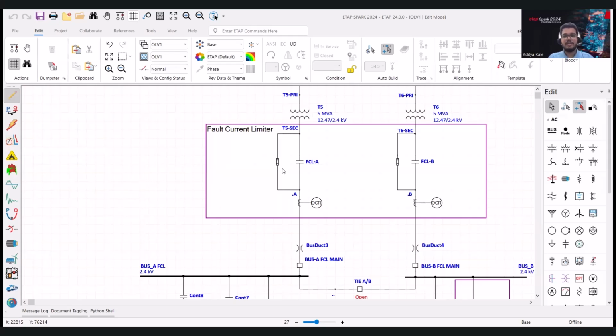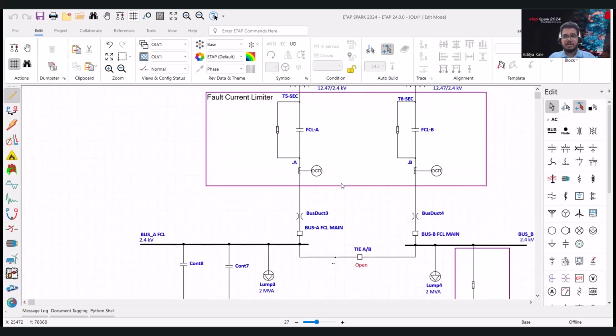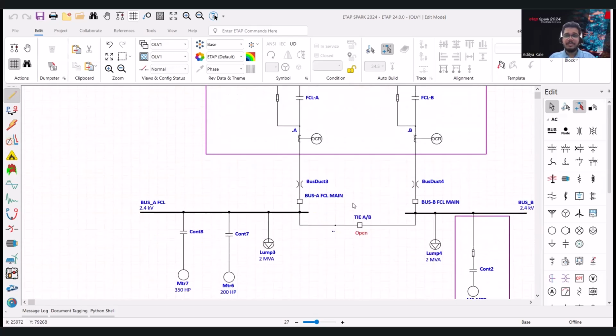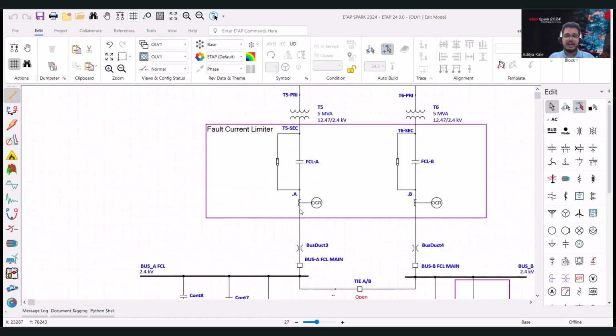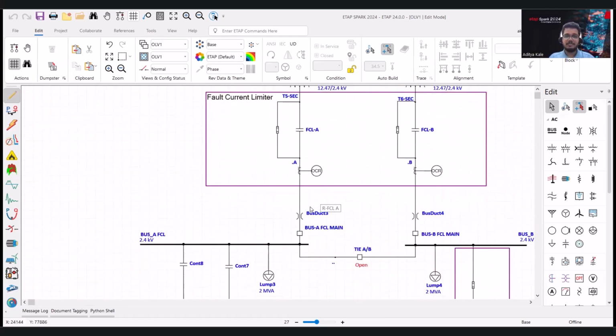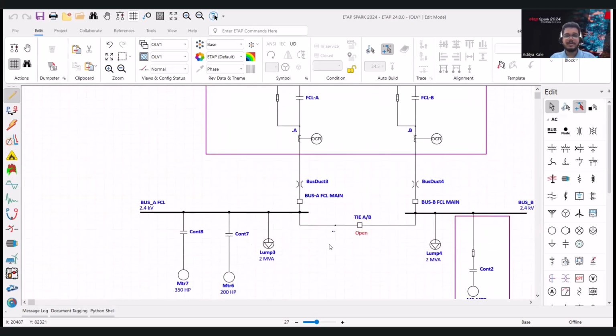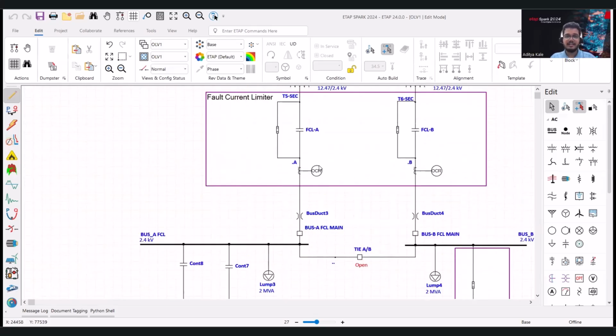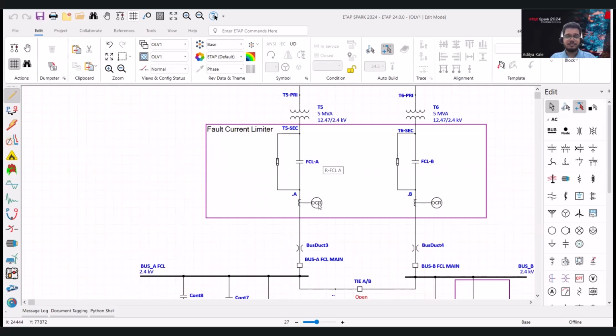It's important to size the fault current limiter carefully, keeping in mind important things such as your load current and any inrush currents that we may have. For our circuit, 10,000 was a safer limit. However, if any of my inrush currents exceeded that 10,000 amps, I would have to rely on the next available size for the fault current limiter.